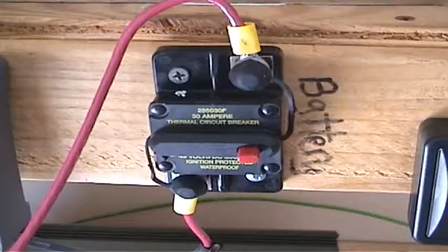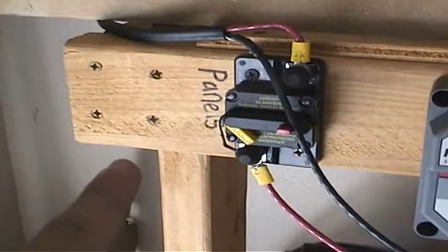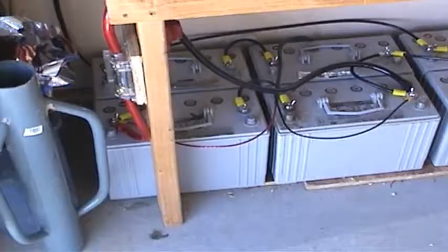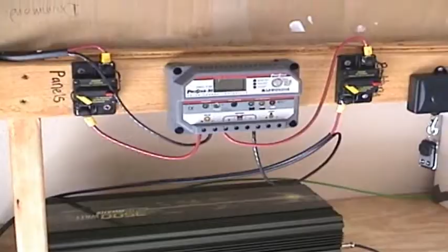Then let's turn the battery to inverter disconnect switch to the off position. Now let's open the circuit breaker marked battery. And finally, let's open the circuit breaker marked panels. Now the inverter is disconnected from the battery bank, the battery bank is disconnected from the solar charge controller, and the solar charge controller is disconnected from the solar panels. Now you can safely complete any maintenance or tinkering on your system.